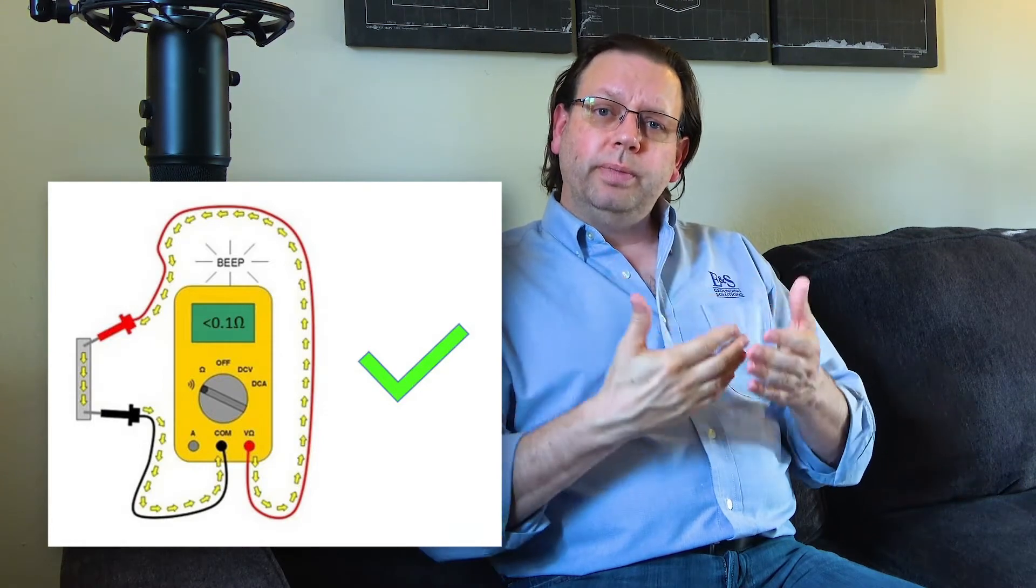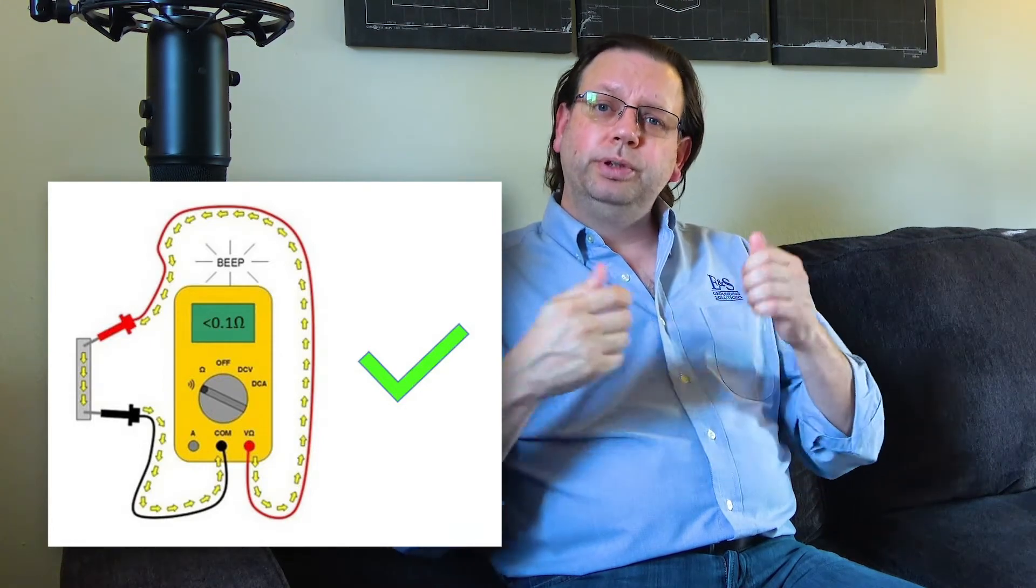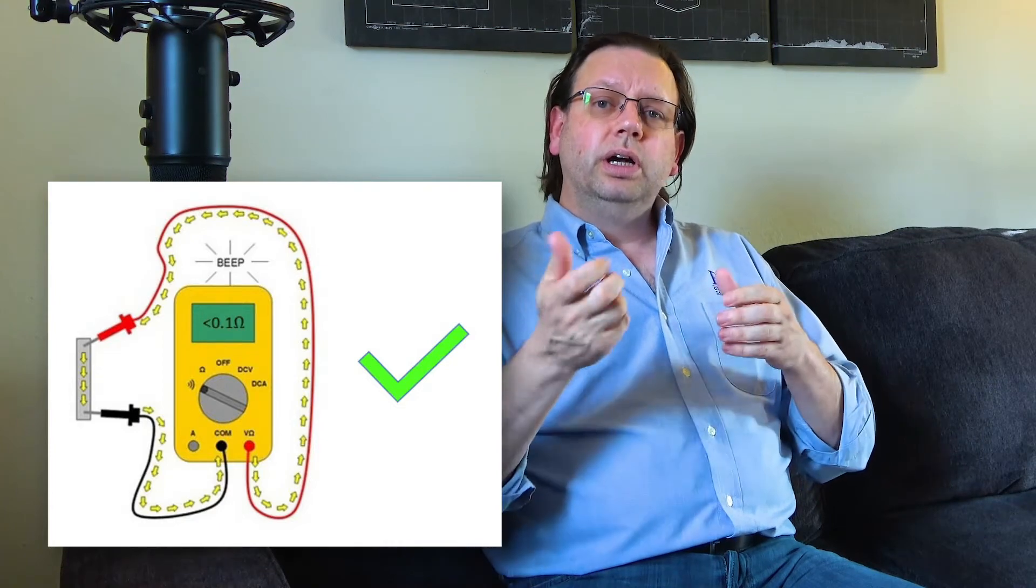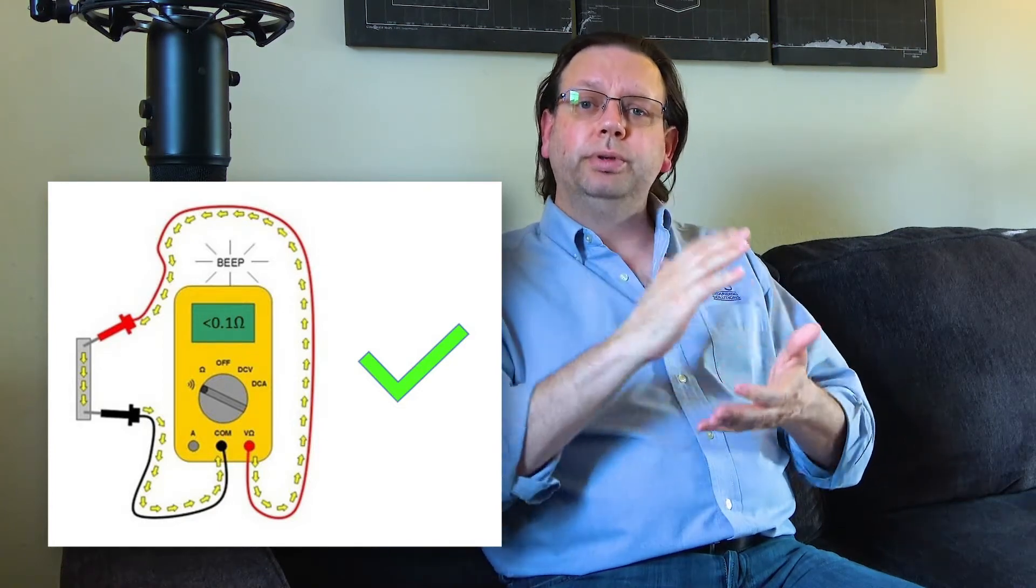Now there's a number of different methodologies behind this. Some people use AC systems with high current. Some people use DC systems that hold and charge, put enough electrons to charge the entire ground system and measure decay rates, what they call an induced polarization system. We tend to like that technique, but there are numerous techniques out there. The ultimate goal, of course, is just to confirm that you do have a nice low path.